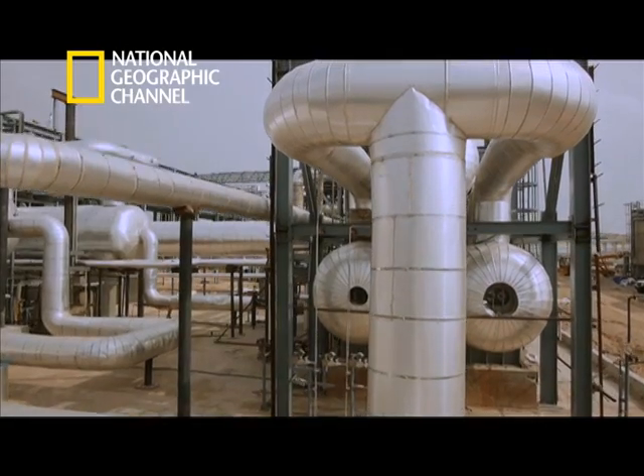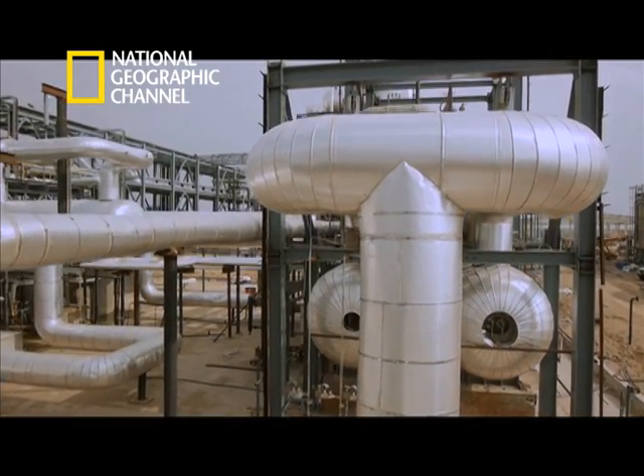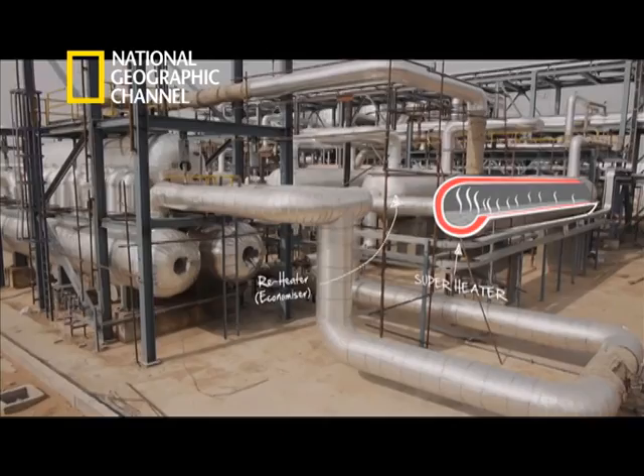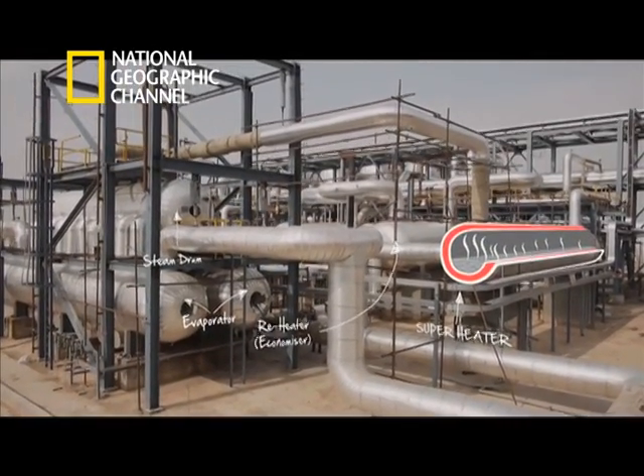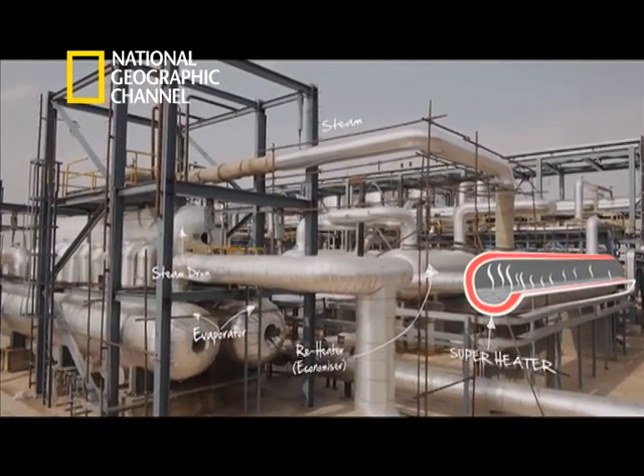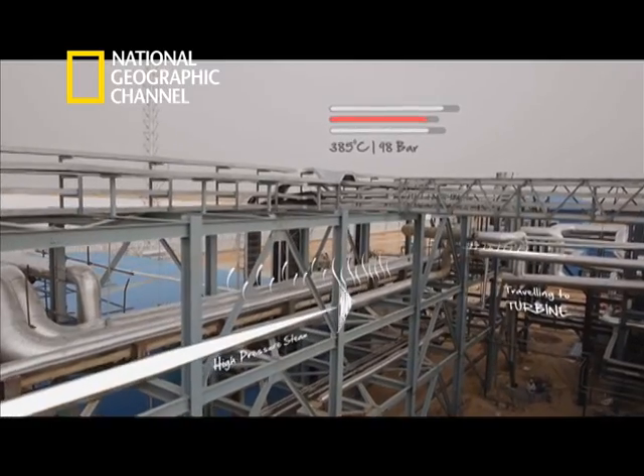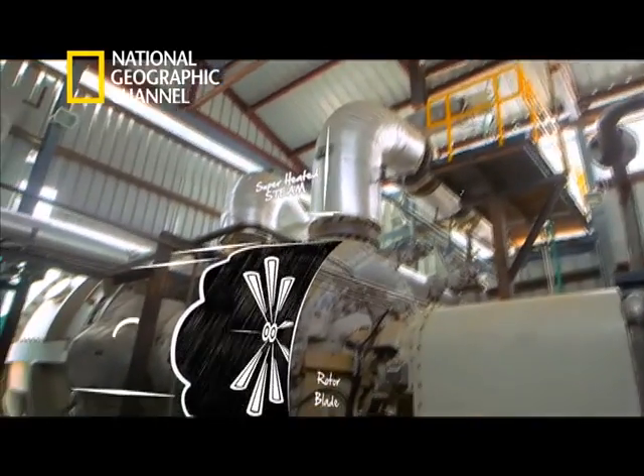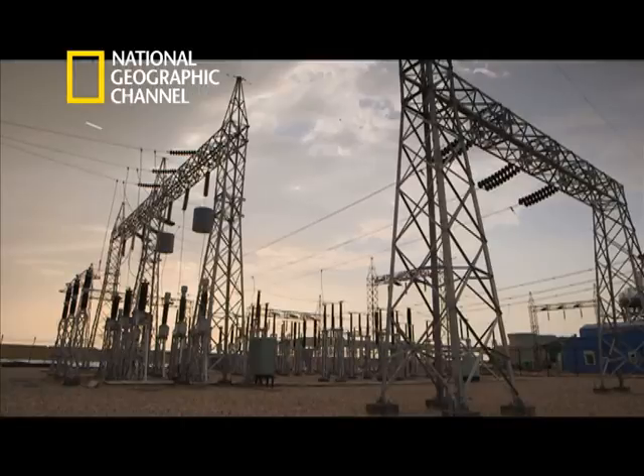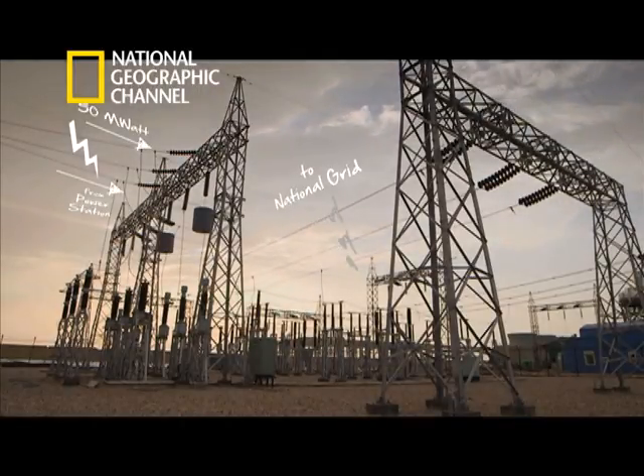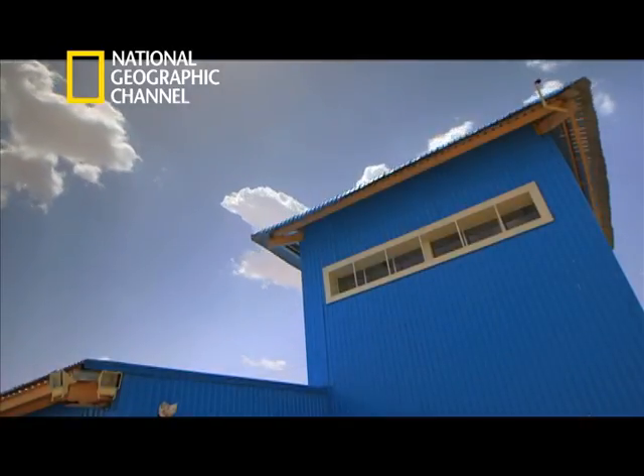Here, pipes containing HTF will exchange heat with 257 tons of water per hour, generating superheated steam up to a temperature of 385 degrees Celsius. This steam will then be used to power the turbine, which will then generate the precious megawatts.